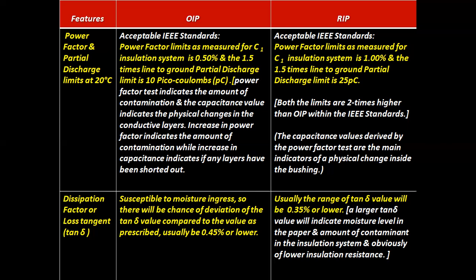Dissipation factor or loss tangent, that is tan delta, is susceptible to moisture. So there will be a chance of deviation of the tan delta value compared to the value as prescribed, usually 0.45% or lower in the case of OIP bushings. For RIP bushings, usually the range of tan delta value will be 0.35% or lower. A larger tan delta value will indicate the moisture level in the paper and the amount of contaminant in the insulation system, and obviously a lower insulation resistance.